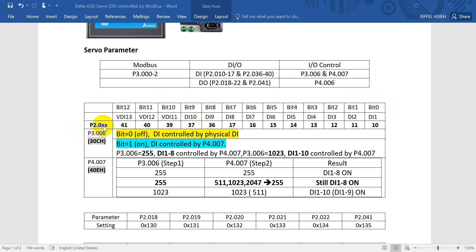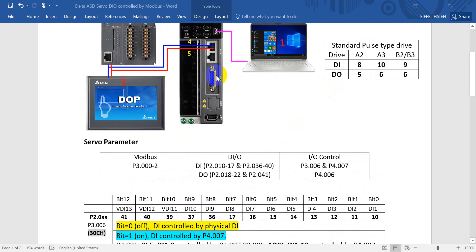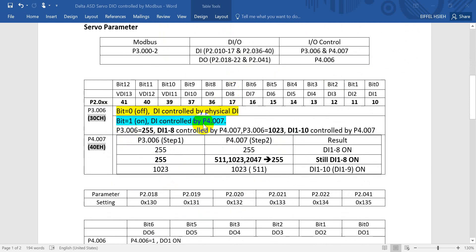This is the corresponding parameters. So DI1 will be defined in P2-010, DI2 in P2-011, DI3 in P2-012. And DI9 corresponds to bit 8, defined in P2-036. Then for P3-006, if we define each bit to 0, the digital input will be controlled by the physical DI — meaning you provide the external signal from CN1. If we want to control by Modbus, then we have to define the bit to 1.